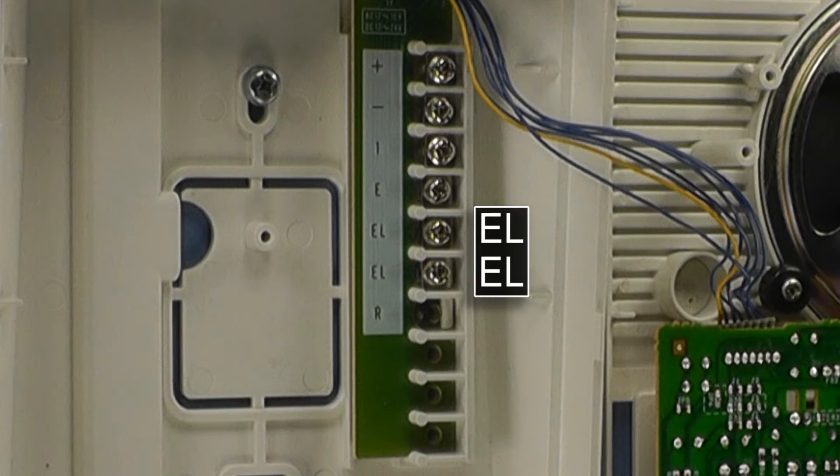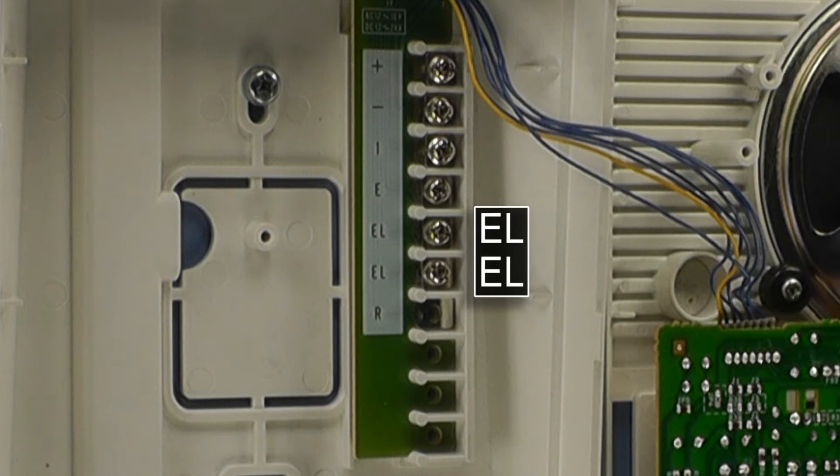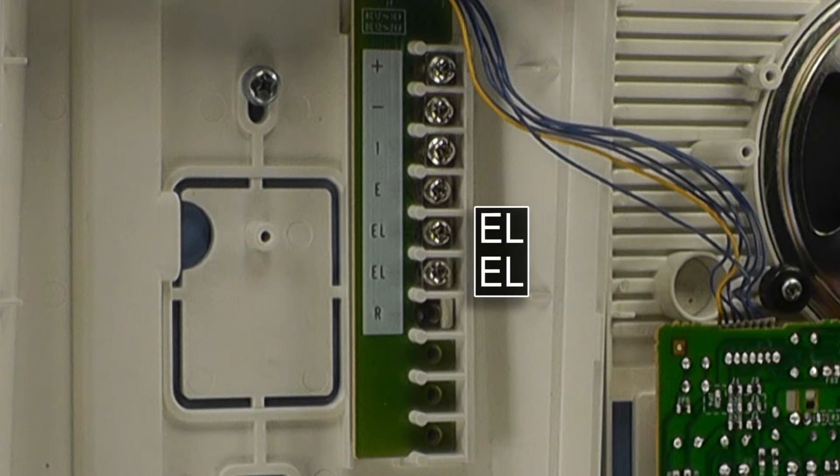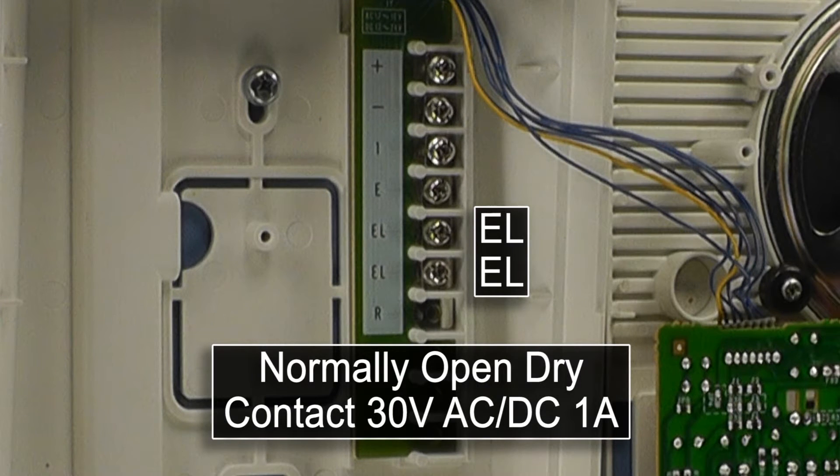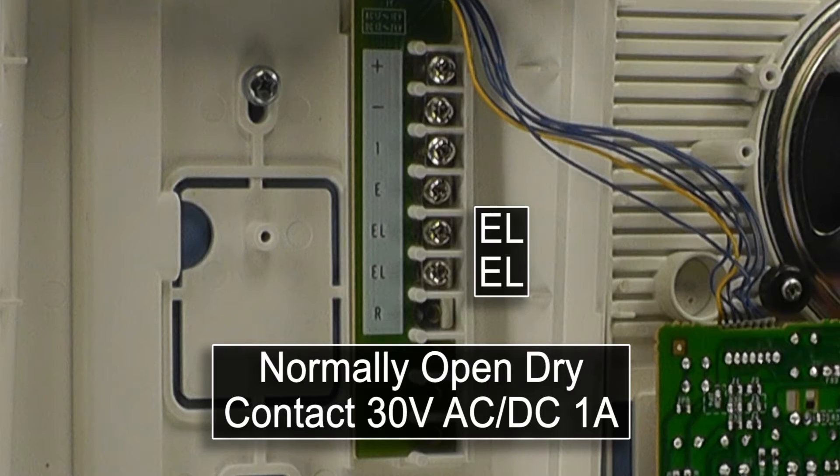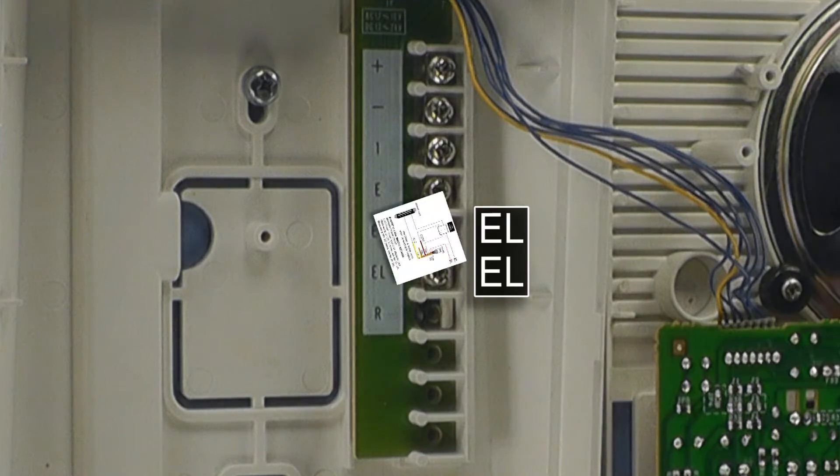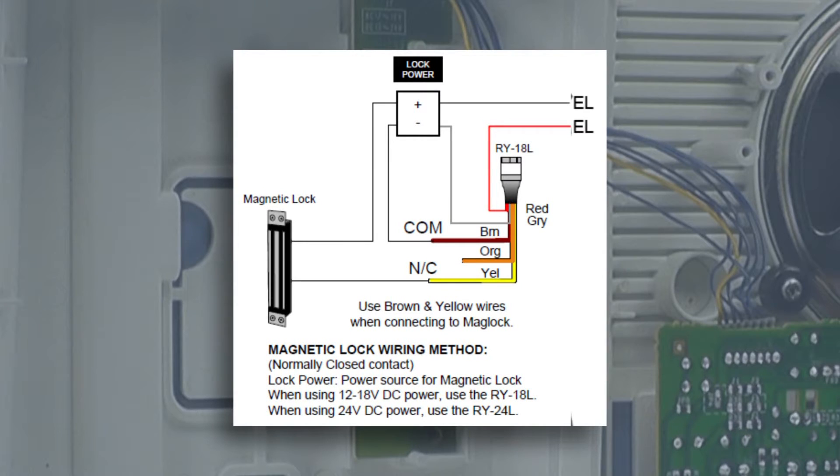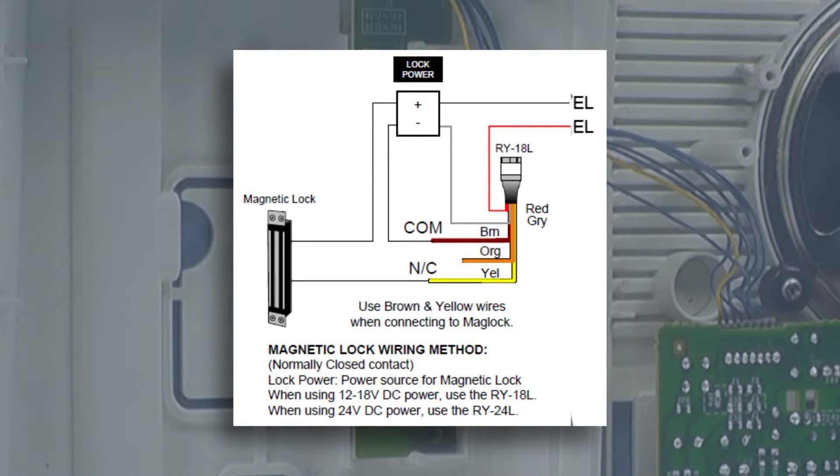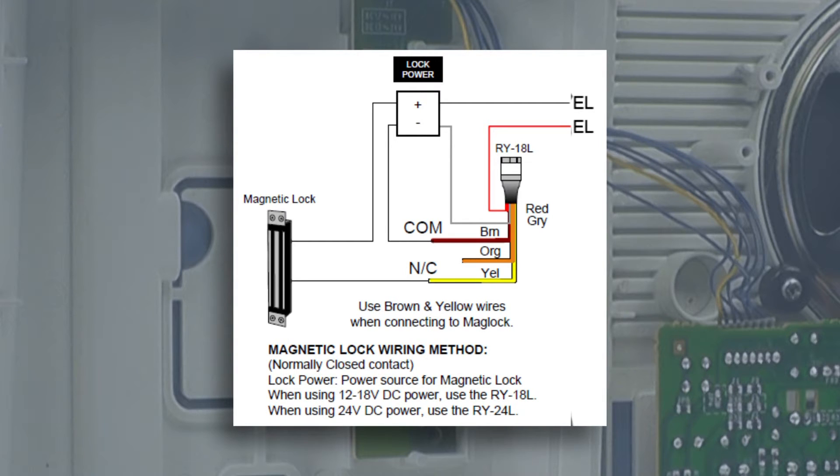At the bottom are the EL terminals, which can be used to unlock a door or a gate. The EL terminals are a normally open dry contact, rated at a maximum of 30 volts AC or DC at 1 amp. If a normally closed contact is desired, such as when triggering a mag lock, you will need to use an external relay wired to the EL terminals. The external relay may require a separate power source.